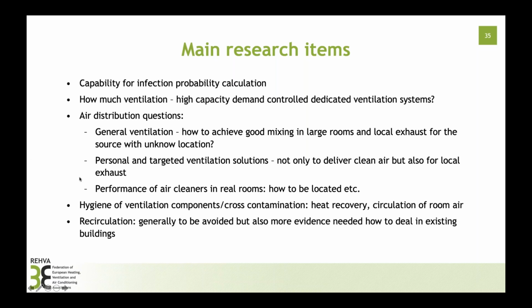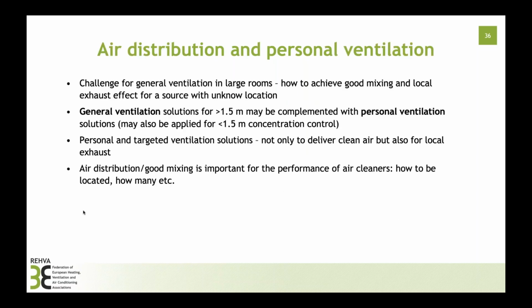Then there are several air distribution questions, and as we already discussed, hygiene of ventilation components and recirculation issues. When coming to air distribution questions, general ventilation solutions generally aim to achieve good mixing, so-called mixing ventilation, but these may be complemented with personal or targeted ventilation solutions. So that in some parts of the rooms, we try to supply more clean air and to have more clean zones, so lower concentrations. And indeed, there are many possible applications for such personal and targeted ventilation solutions. But this also applies to local exhaust. These local exhaust effects can also be important in virus concentration reduction.